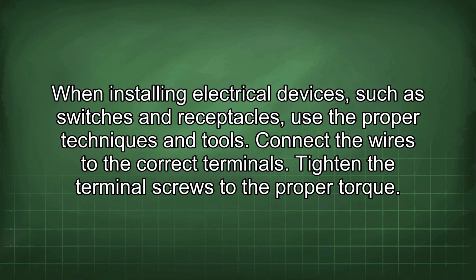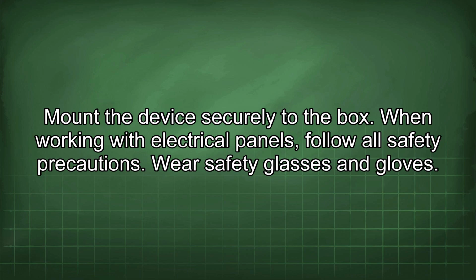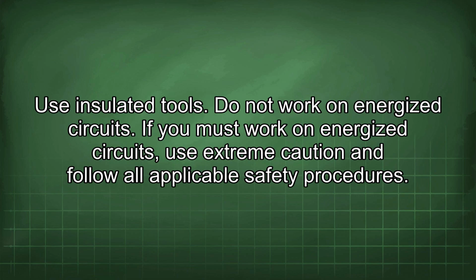When installing electrical devices, such as switches and receptacles, use the proper techniques and tools. Connect the wires to the correct terminals. Tighten the terminal screws to the proper torque. Mount the device securely to the box. When working with electrical panels, follow all safety precautions. Wear safety glasses and gloves. Use insulated tools. Do not work on energized circuits. If you must work on energized circuits, use extreme caution and follow all applicable safety procedures.